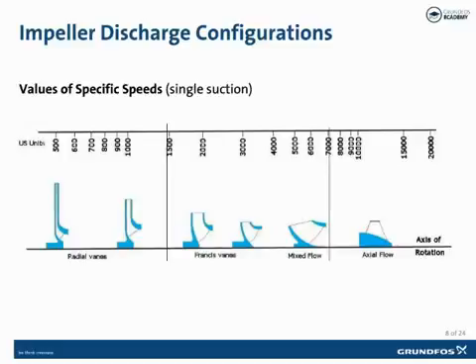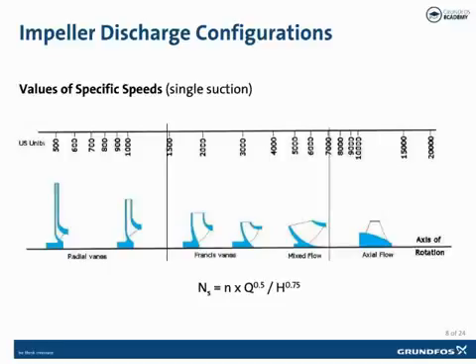The lower values, 500 to 1,500, pertain to the geometry associated with radial vane type impellers. The middle values, 1,500 to 7,000, are typical for Francis vane and mixed flow type impellers. Higher values, 7,000 to 15,000, are typical for axial flow type impellers. Note that as we progress from left to right, the impeller inlet approaches the size of the outlet for the impeller. Here's the equation for specific speed.